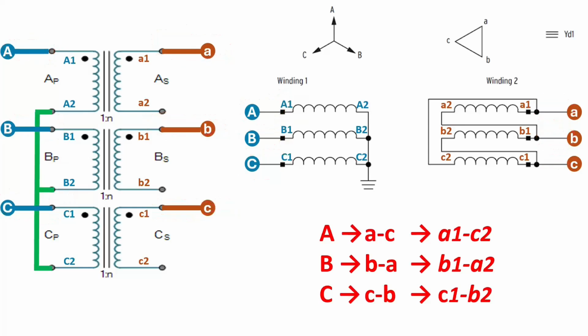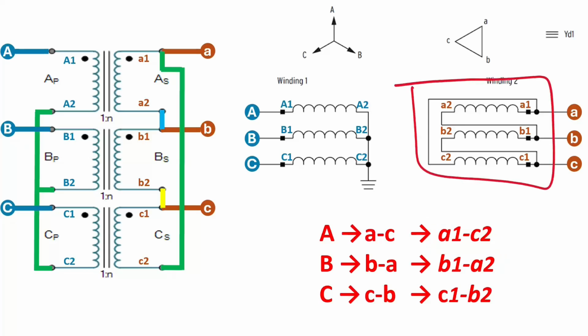So now we know that our primary is a Y. So we're just going to jumper all of our twos together. Okay, that's too easy. And then the next one we're going to do is build our delta on the secondary. And if you look, we've already shown this designation, but let's just actually use the YD1. This diagram, by the way, came out of the SEL 587 relay manual, so it's not something that I just fudged and made up. All I did was add some designations, which we could redefine as anything we want, as long as we maintain the connection diagram.